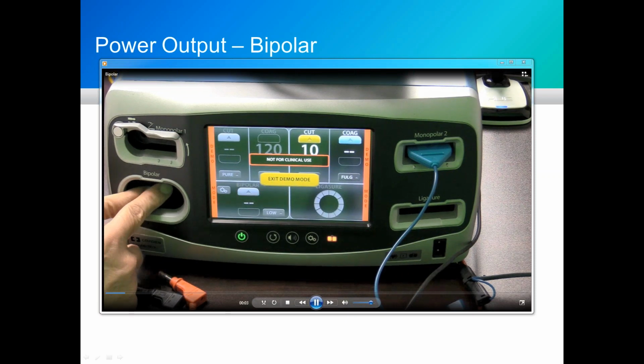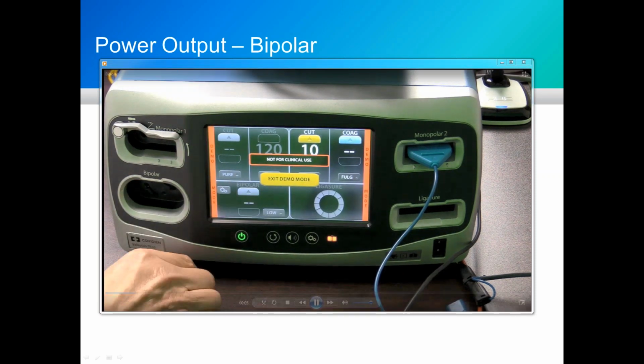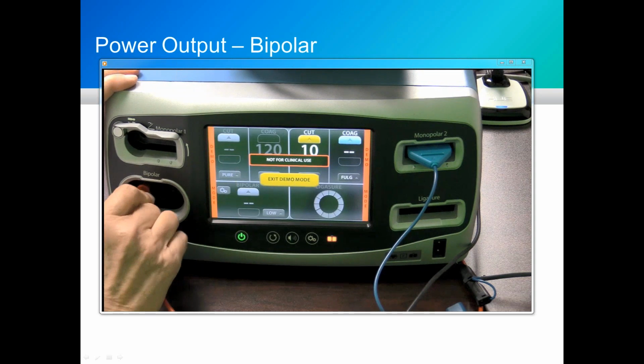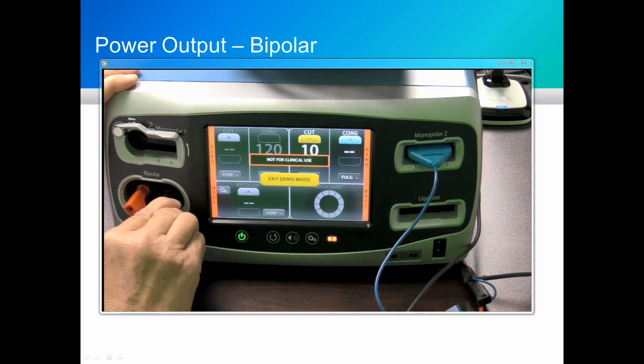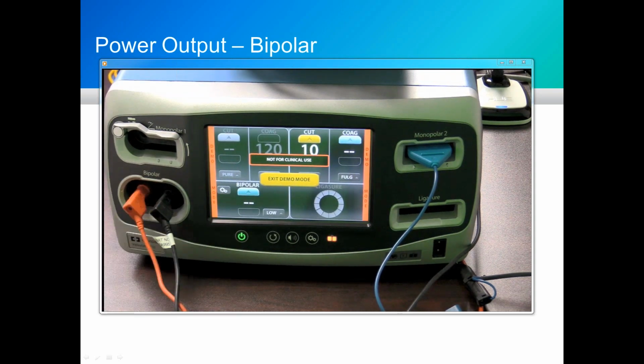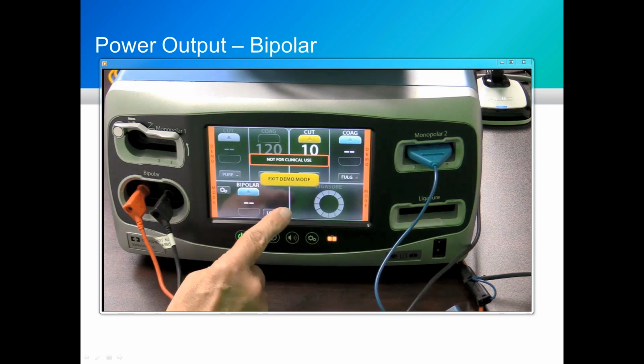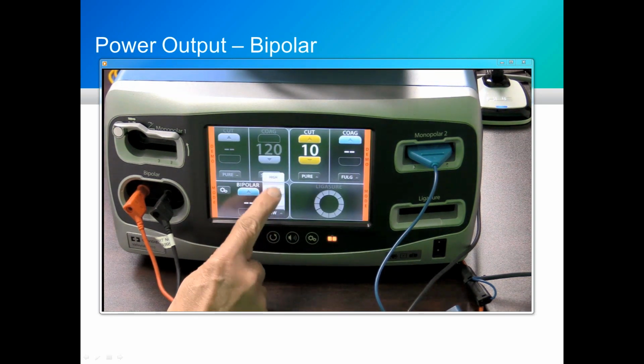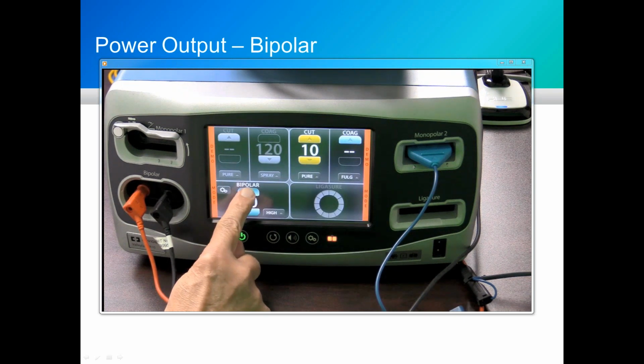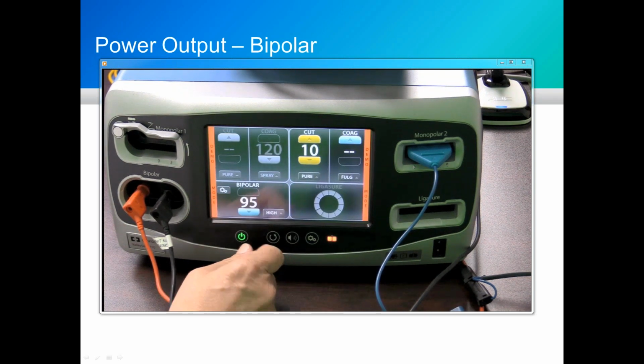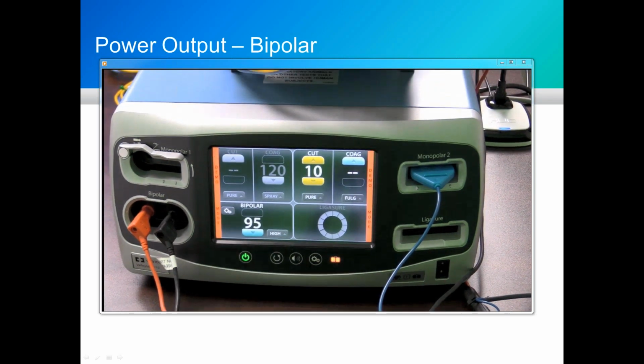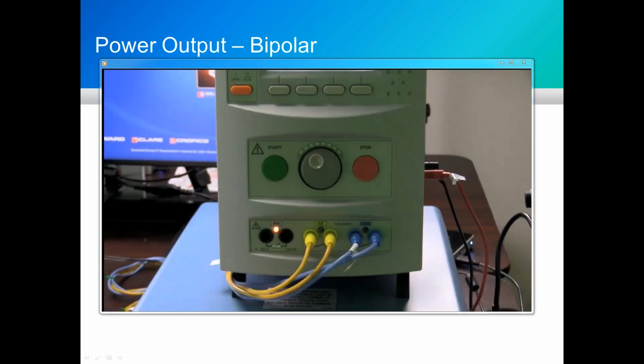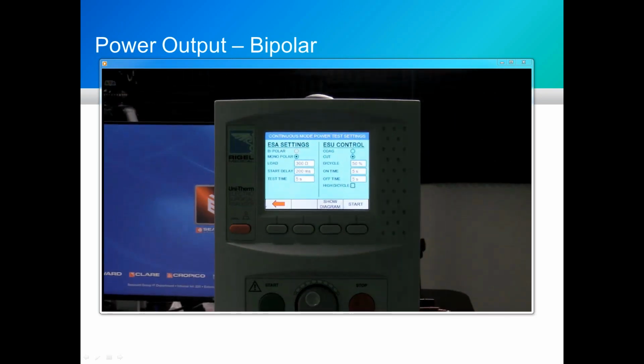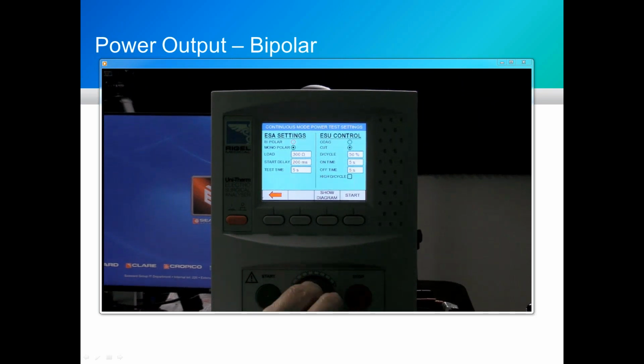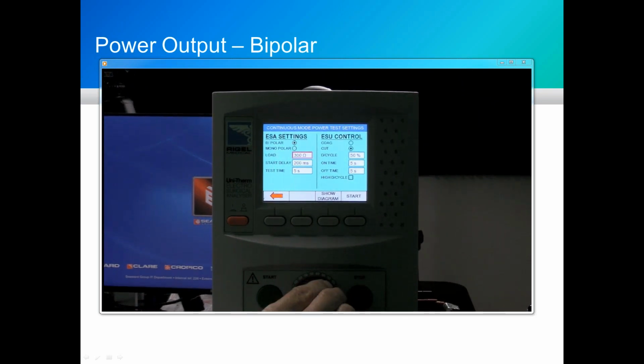Notice here we have 2 little micro switches, and sometimes a right angle lead as I'm plugging in will not capture both of those closed. So just reach in, latch them, and you see that bottom quadrant of the display become active. So I'm going to go to the highest power setting. I'm going to select bipolar. I'm going to reset my load resistance.